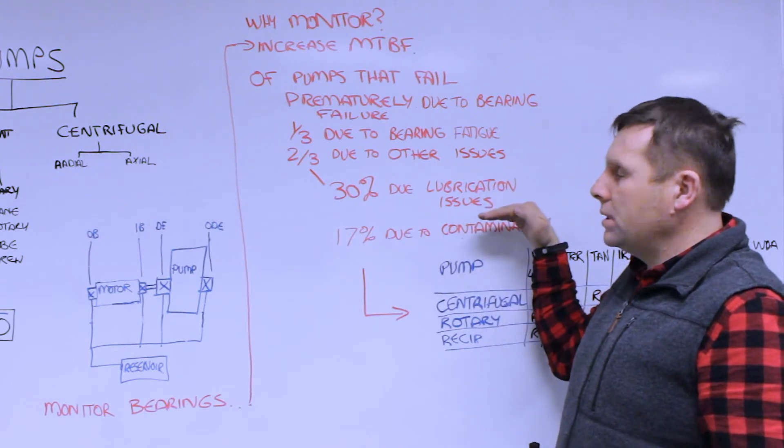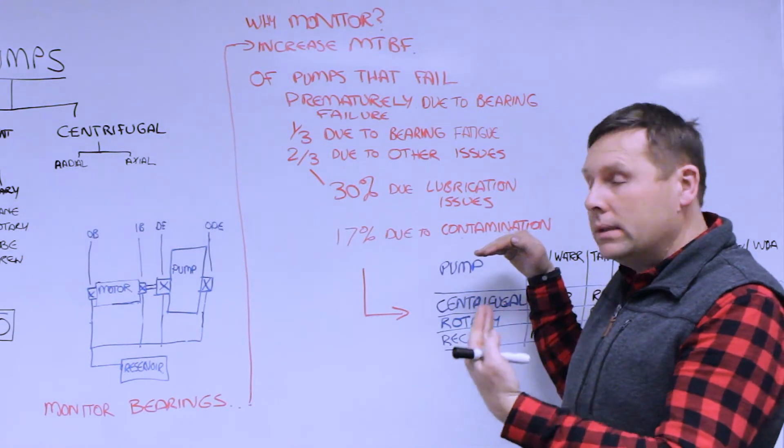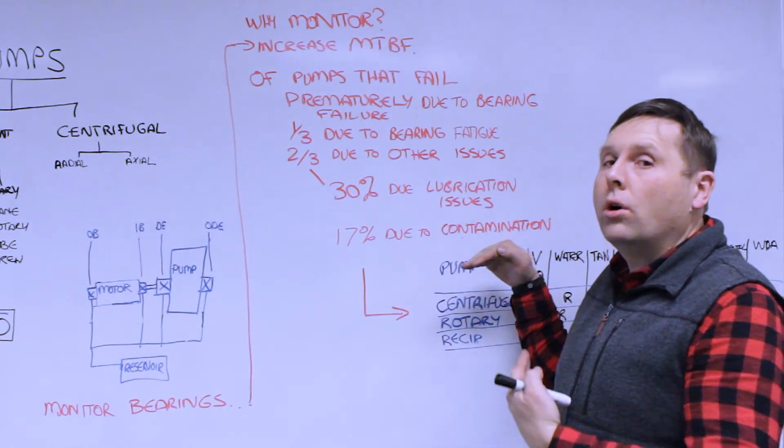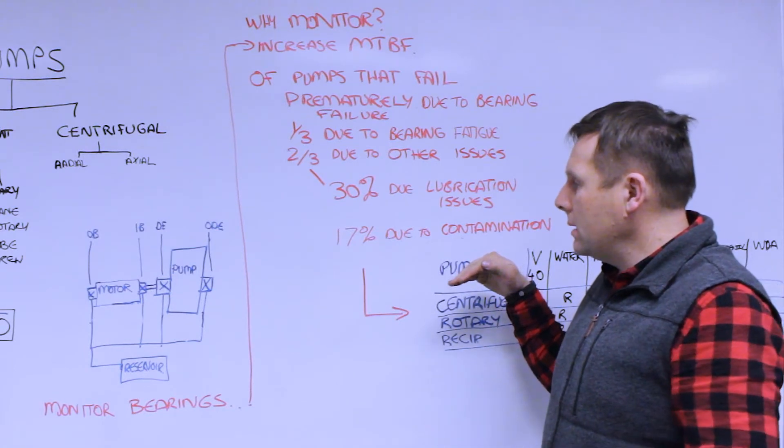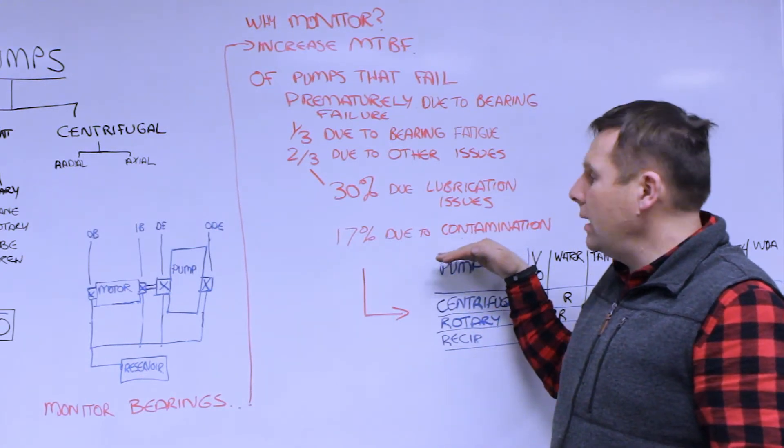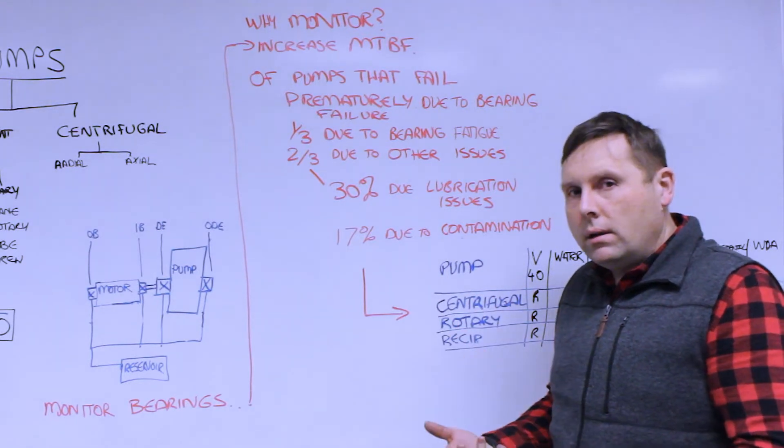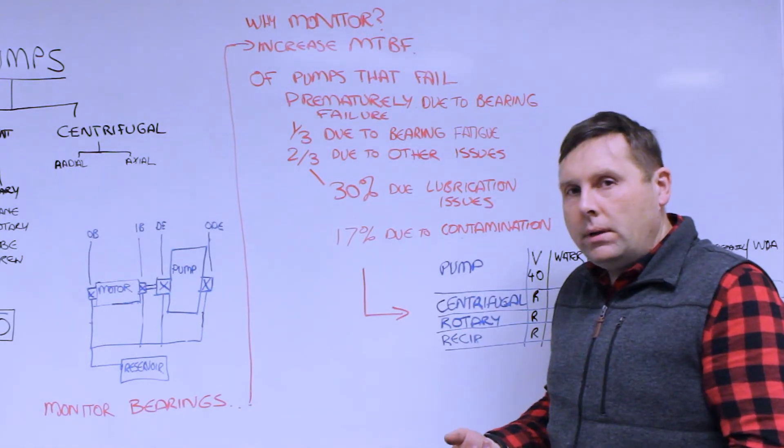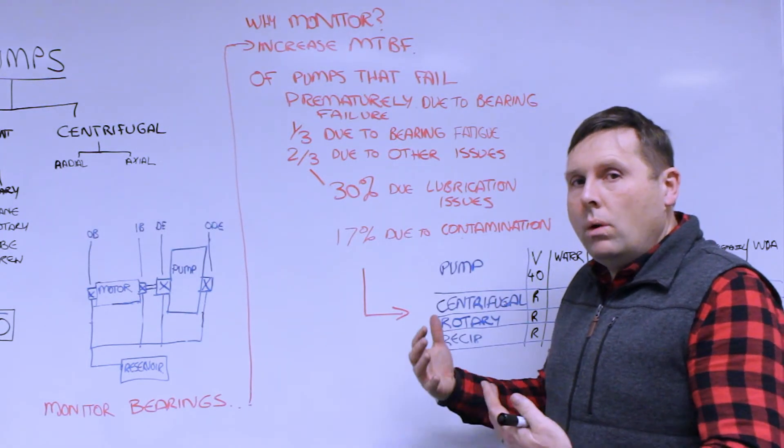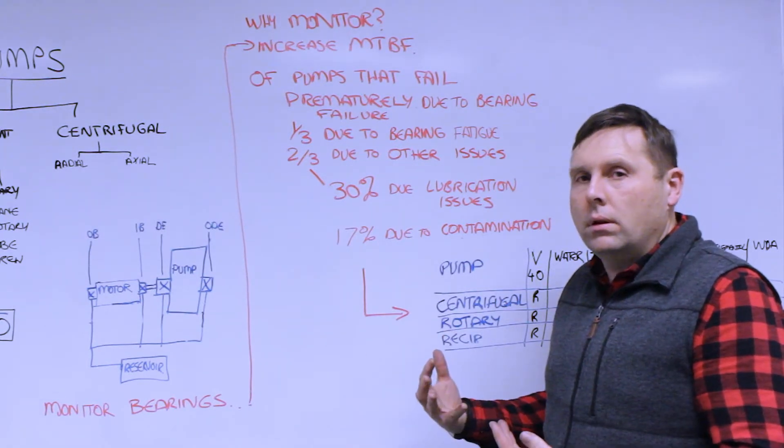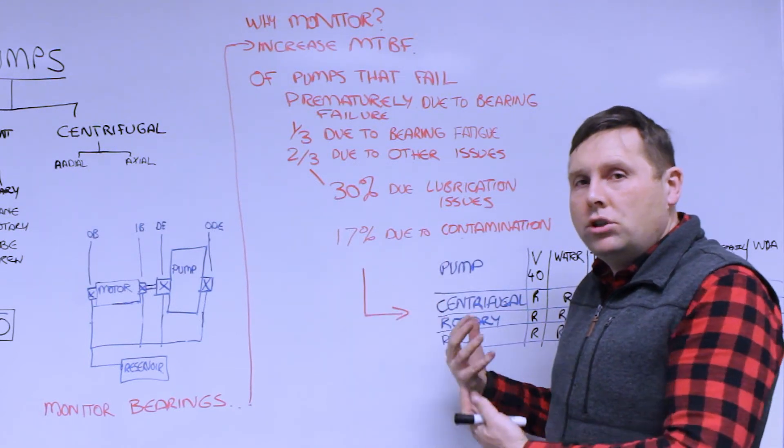Of those other issues, 30% is lubrication related. That could be the wrong lubricant, the lubricant degraded past its point, or no lubricant in the pump bearing system. And 17% is due to contamination, such as air getting in, particulates, or water contamination. As a result, when we're monitoring for contamination in these issues, we want to check with oil analysis.